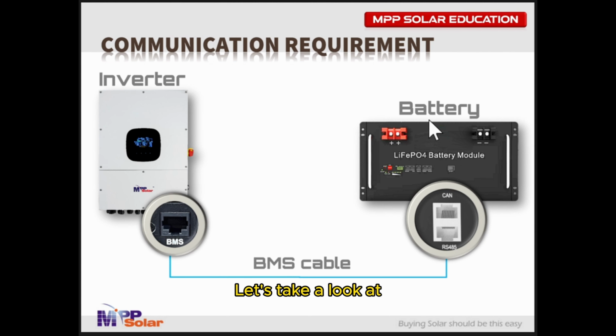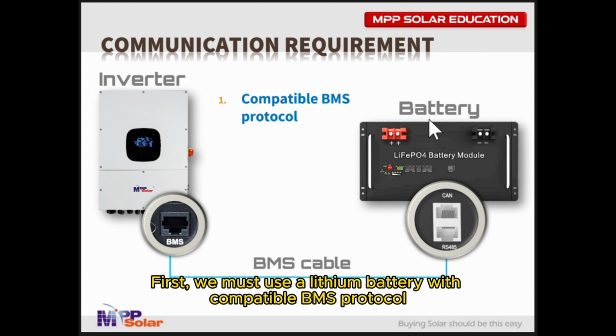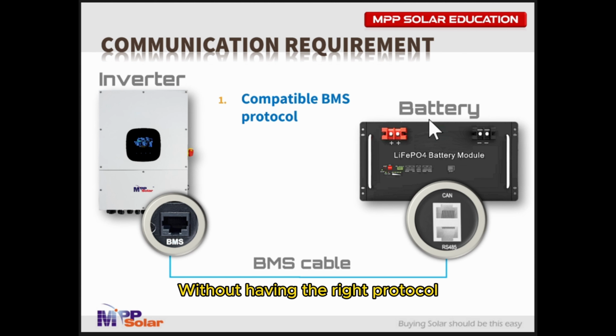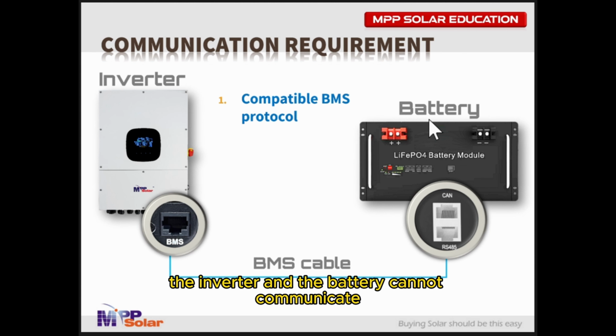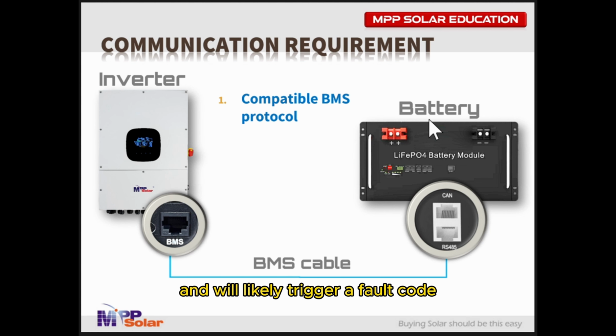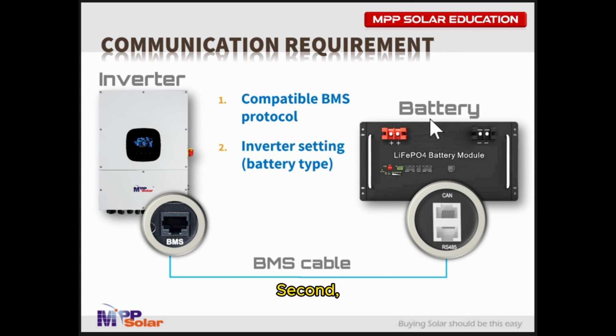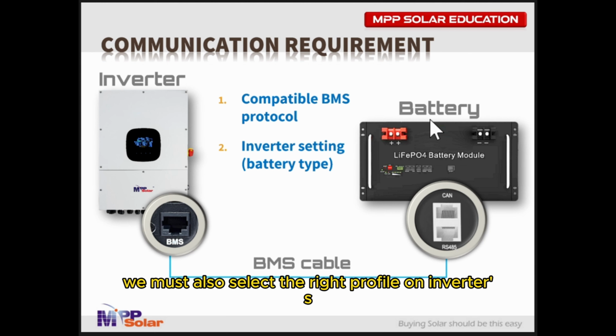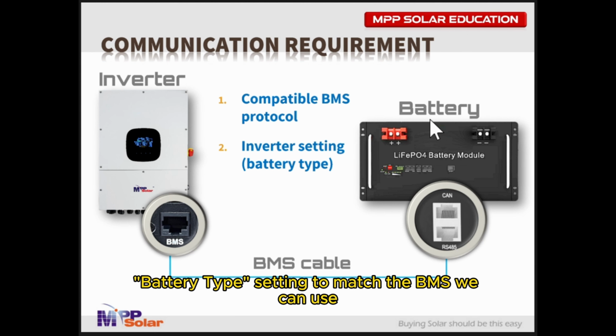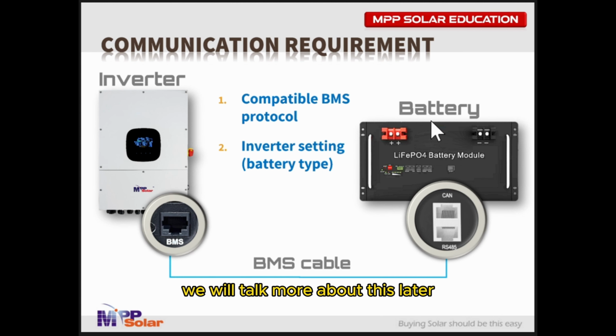Let's take a look at the typical setup of a BMS connection in an inverter system. There are three things we should keep in mind when setting up BMS. First, we must use a lithium battery with a compatible BMS protocol. Without having the right protocol, the inverter and the battery cannot communicate and will likely trigger a fault code. Second, we must also select the right profile in the inverter's battery type setting to match the BMS we are using. We will talk more about this later.